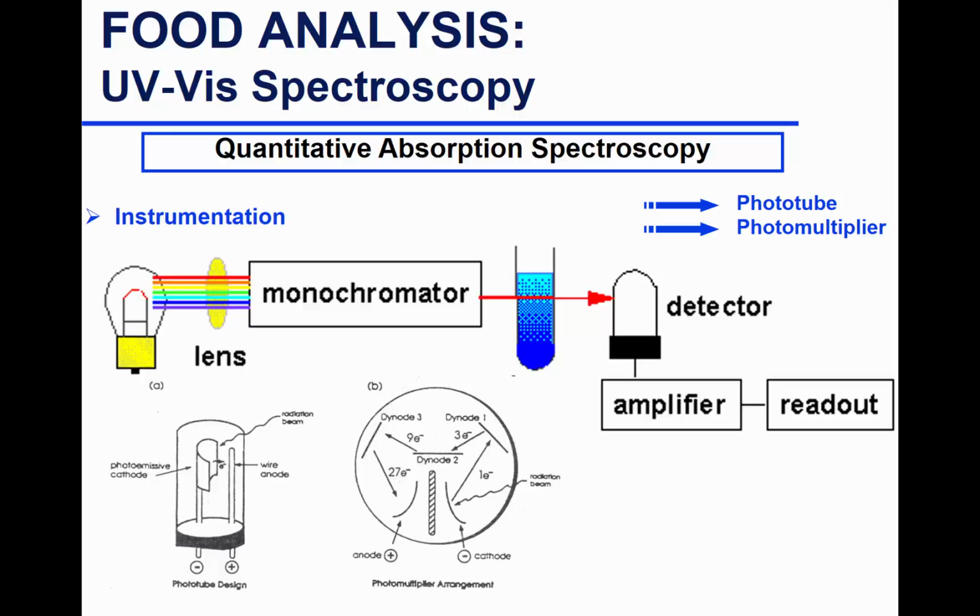However, if you want to amplify sensitivity, or reduce the threshold, you do an amplification, so a photomultiplier. The beam of light hits the cathode, an electron hits a dynode, and more electrons jump off of that into a second one, and it keeps increasing. The number of electrons increases every time it hits a dynode.